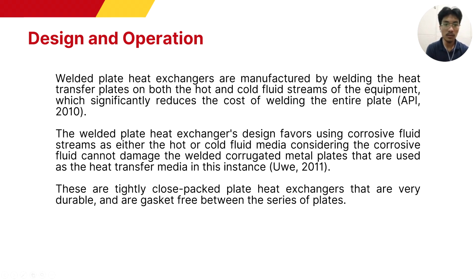These metals include stainless steel, nickel, titanium, carbon steel, and many more. Also, the corrugated metal pattern on the welded plates significantly reduces the accumulation of deposits on the plates themselves. This then results in a lesser probability of corrosion or rusting. Moreover, the primary type of welding used in this welded plate heat exchanger is laser welding or argon arc welding.